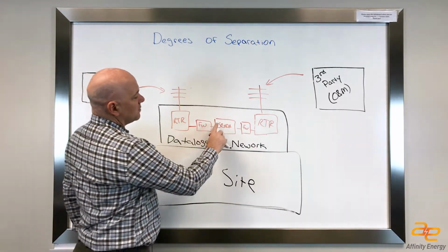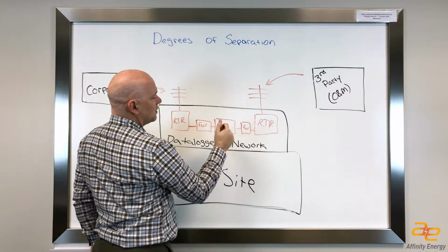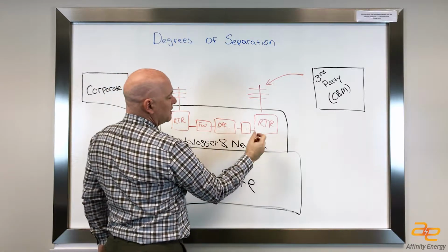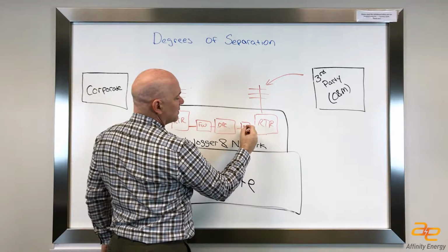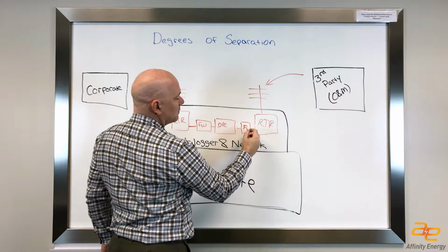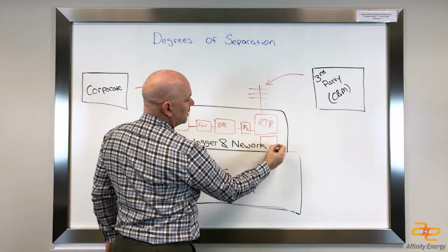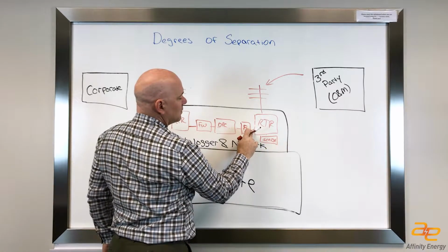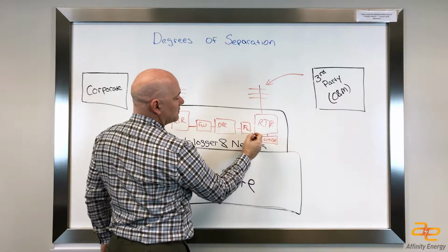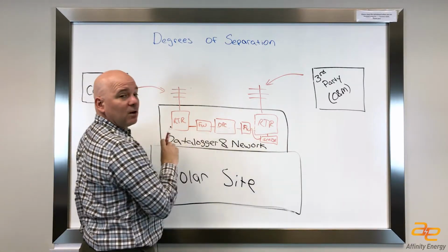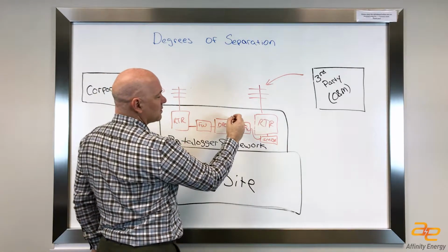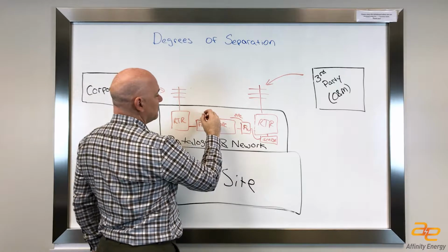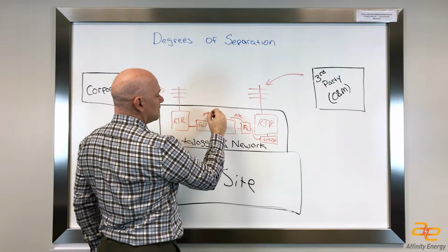security, what you could do, instead of having SCADA here, is have an OPC server here. And then on this side, we're going to put in a firewall here, and I'm going to put in a SCADA computer down here, so the router talks to SCADA, SCADA talks to the firewall, the firewall talks OPC, and now this firewall is configured to only allow OPC traffic. This firewall is configured to only allow Modbus traffic.